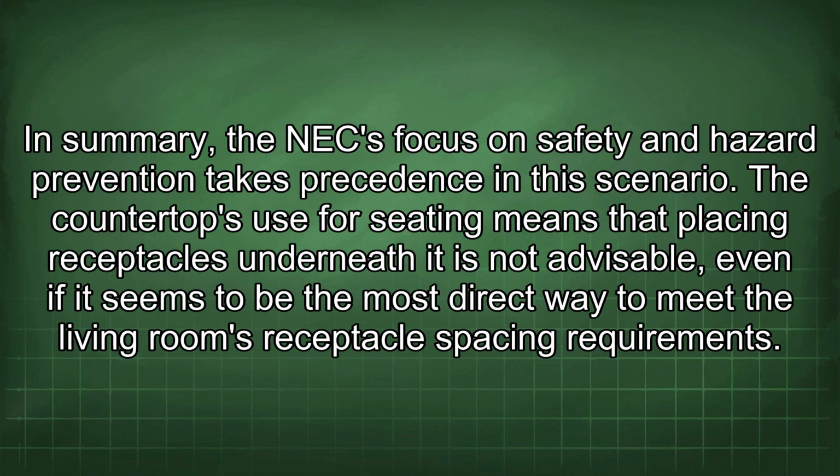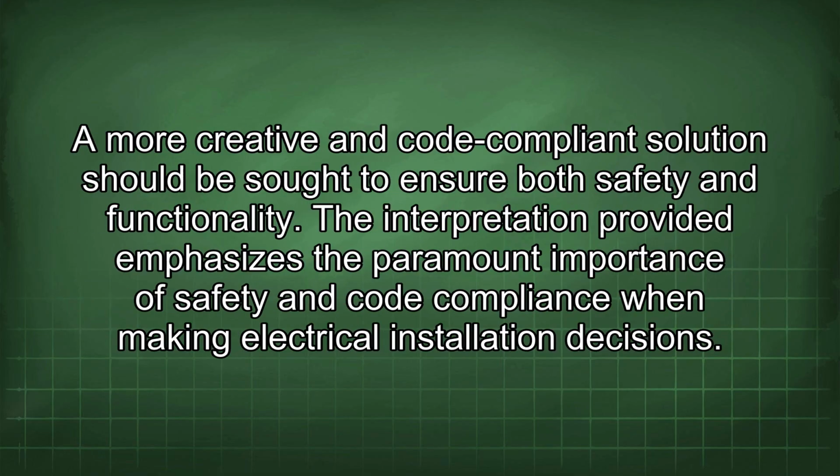In summary, the NEC focus on safety and hazard prevention takes precedence in this scenario. The countertop's use for seating means that placing receptacles underneath it is not advisable, even if it seems to be the most direct way to meet the living room's receptacle spacing requirements. A more creative and code-compliant solution should be sought to ensure both safety and functionality. The interpretation provided emphasizes the paramount importance of safety and code compliance when making electrical installation decisions.